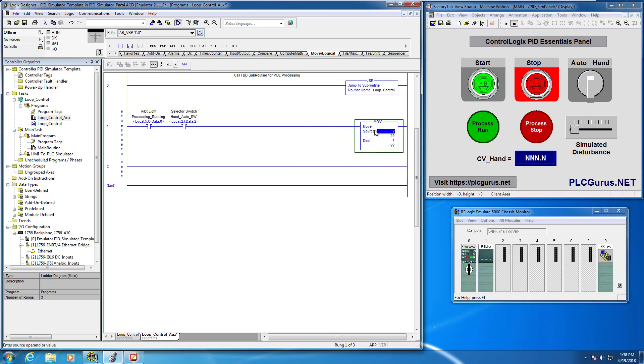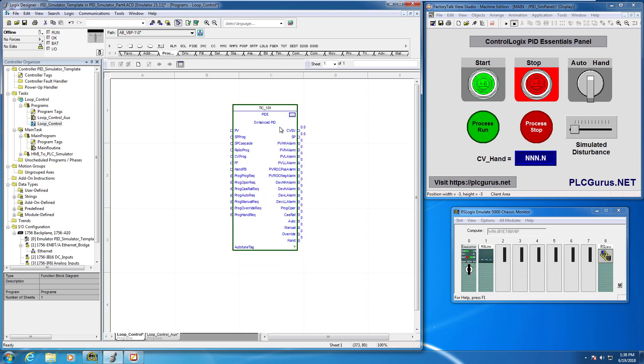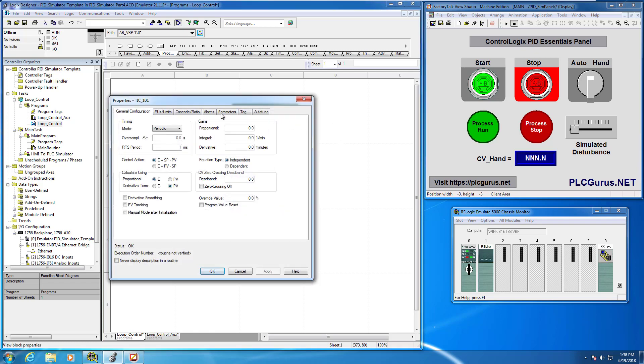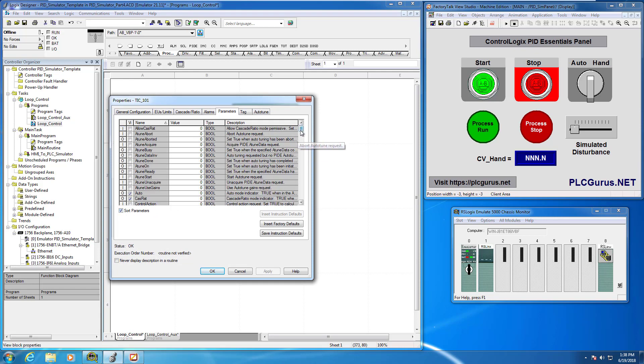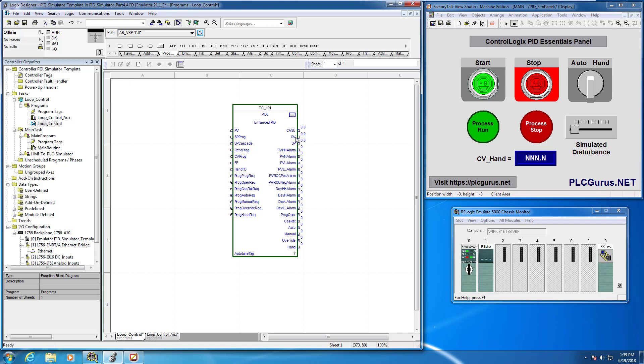Now I want to take the cv value. Going back to loop control, notice there's something called 'cveu' which is a pre-scaled version. For this video, to give exposure to a few more instructions, I'm going to use the 'cv' variable to drive the output instead. If you go into parameters and sort alphabetically, you'll find 'cv' — this is an unscaled value and we'll do the scaling ourselves with a scaling instruction. Click apply and it will become visible on the instruction.